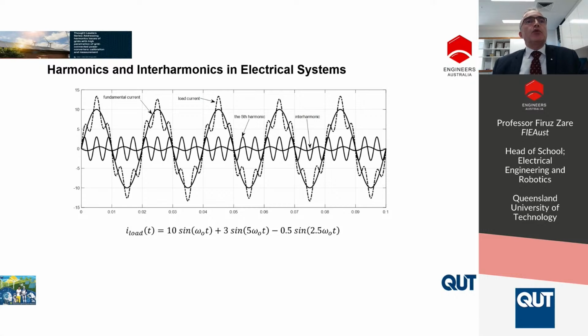Basically according to IEC and IEEE standardization, harmonics are defined up to order of 40th based on IEC or 50th based on IEEE. But recently we have received lots of complaints in terms of harmonic issues at high frequency. So therefore, according to IEC, harmonics are defined below 9 kilohertz. And there are different measurement methods based on grouping that I will explain later during my presentation.